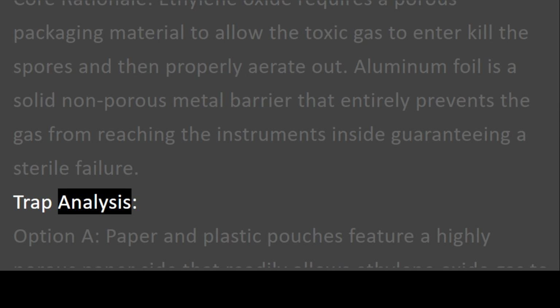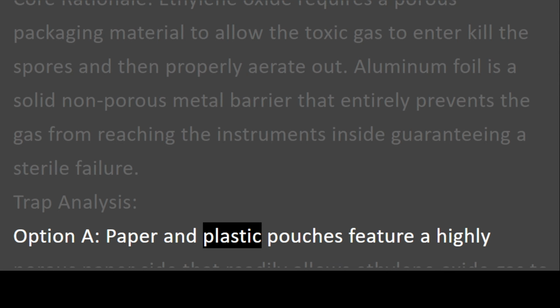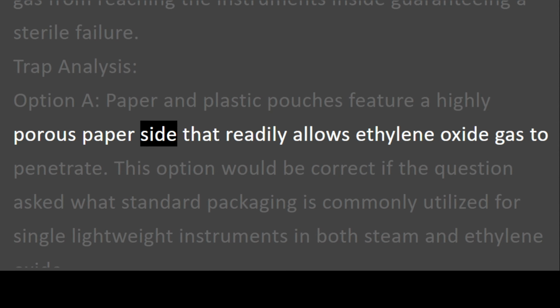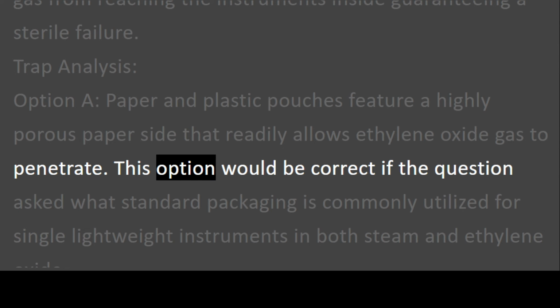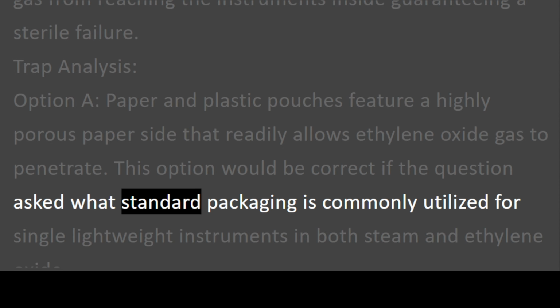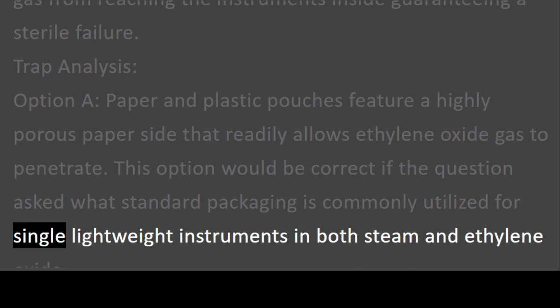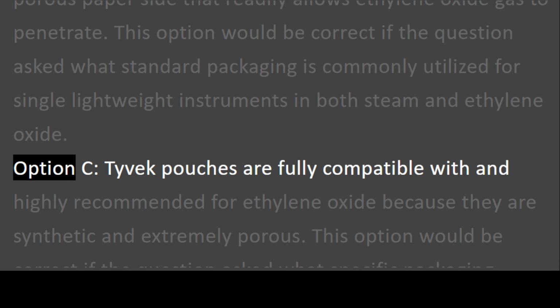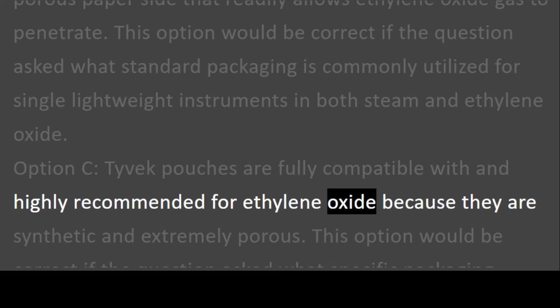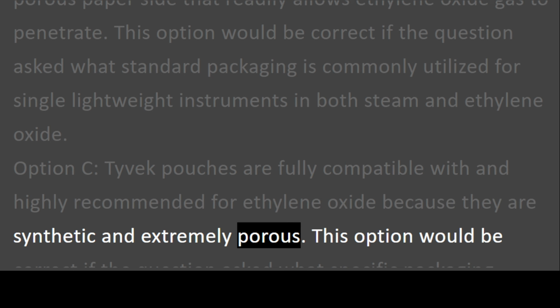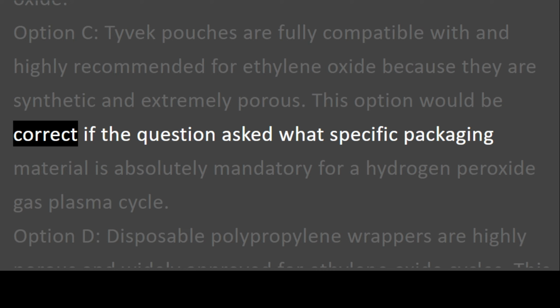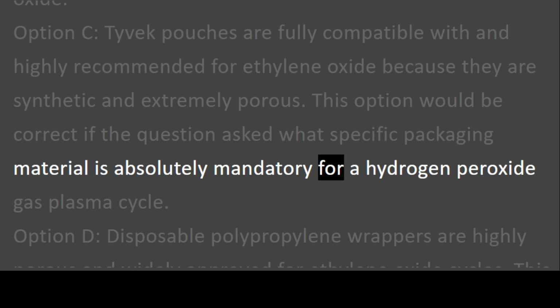Trap analysis. Option A. Paper and plastic pouches feature a highly porous paper side that readily allows ethylene oxide gas to penetrate. This option would be correct if the question asked what standard packaging is commonly utilized for single lightweight instruments in both steam and ethylene oxide. Option C. Tyvek pouches are fully compatible with and highly recommended for ethylene oxide because they are synthetic and extremely porous. This option would be correct if the question asked what specific packaging material is absolutely mandatory for a hydrogen peroxide gas plasma cycle.